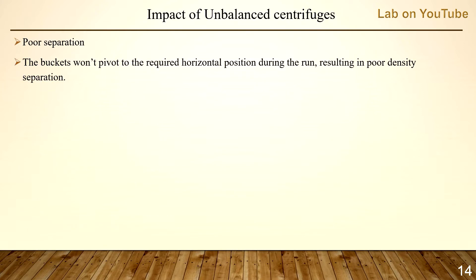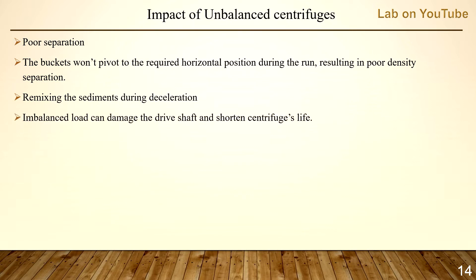The third parameter is balance during centrifugation. Balanced load during centrifugation is very important because improper distribution of tubes in carriers or adapters can cause poor separation. The buckets won't pivot to the required horizontal position during the run, resulting in poor density separation and remixing of sediments during deceleration. Imbalanced load can also damage the drive shaft and shorten the centrifuge's life.